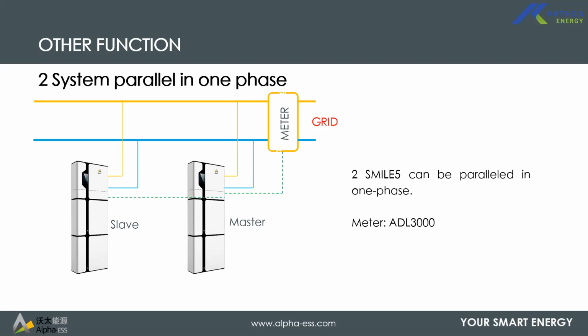But the backup side of the inverter is separate. So it means you would have two separate backup ports for the inverters. But the non-critical side, which is the loads before the inverter, the grid, the live and the neutral are common for both inverters. So you basically have a 10 kilowatt backup on the non-essential side, and then you would have a 2x5 backup system on the backup side. Please note, when these systems are connected in parallel, grid charging is not possible. You cannot charge your batteries from the grid.